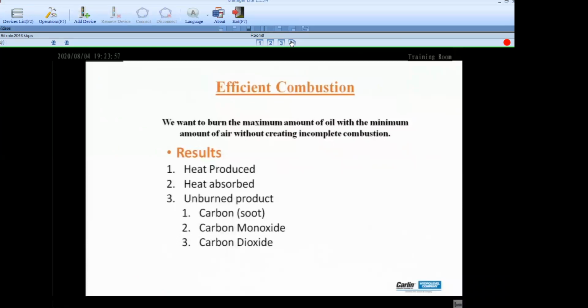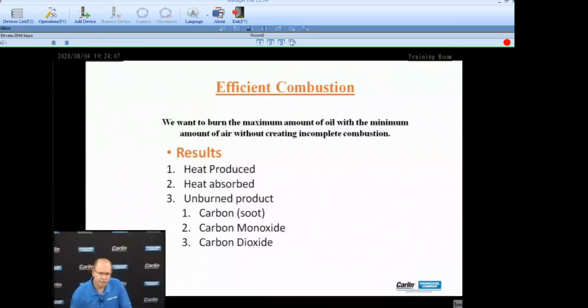So how much heat was produced by the combustion process? How much of that heat was absorbed by the appliance? And then we look at our unburned product. There shouldn't be any soot. Today's modern equipment operates clean, so there's no soot. Is the carbon monoxide level acceptable? There's always going to be some carbon monoxide in the results. Sometimes it might even say 0. If it says 0, it may not necessarily be 0. It may be that our instruments are not sensitive enough to see those very, very small amounts.